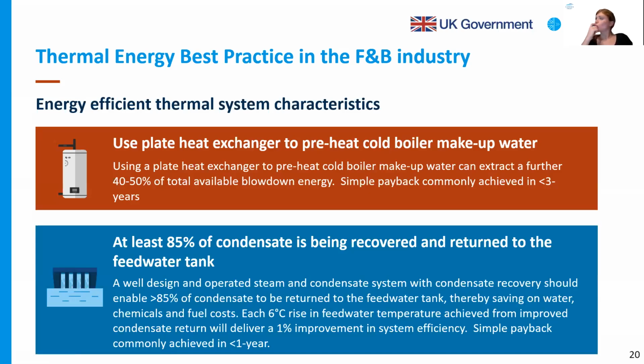So one other option is also to use plate heat exchangers to heat up the cold boiler makeup water, either by using blowdown water or if there is any surplus vented steam in the plant to increase the boiler efficiency. Especially if you have existing plate heat exchangers within the plant, they can be retrofitted, or piping can be rerouted to use them for preheating makeup water.